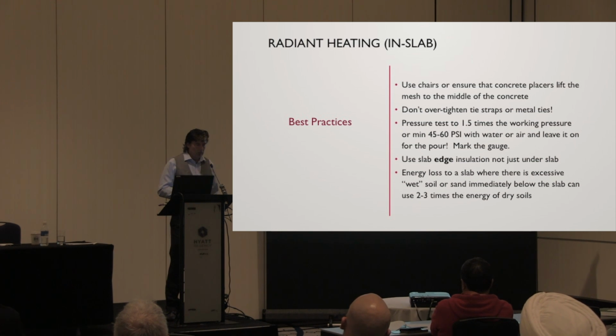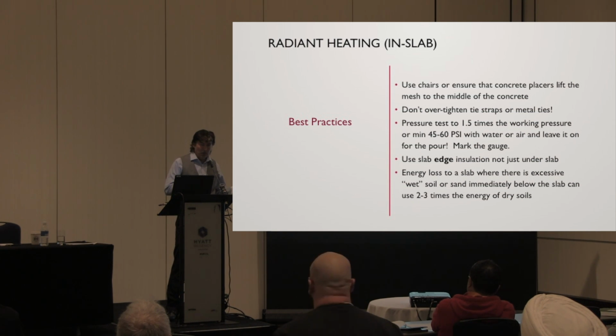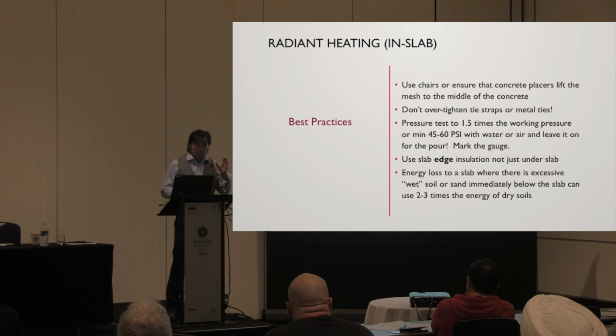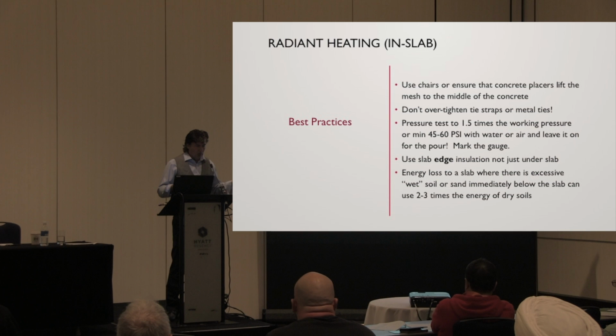I see this a lot in installing floors on wire mesh. You're usually putting the wire mesh there only to hold the radiant. I don't know if it's required structurally. Well, the guys go around and back in the day used a lot of wire ties, like rebar ties, and just crank on those, or even now with the nylon zap straps, to really pull on those. That pipe's not going anywhere. Really don't need to do that. I know it's tempting for everybody to just tighten it right down. It's only really on the turns to hold them in place, and even then you don't have to really cinch them. They've had some issues in Europe that have been reported with people over tightening these things.